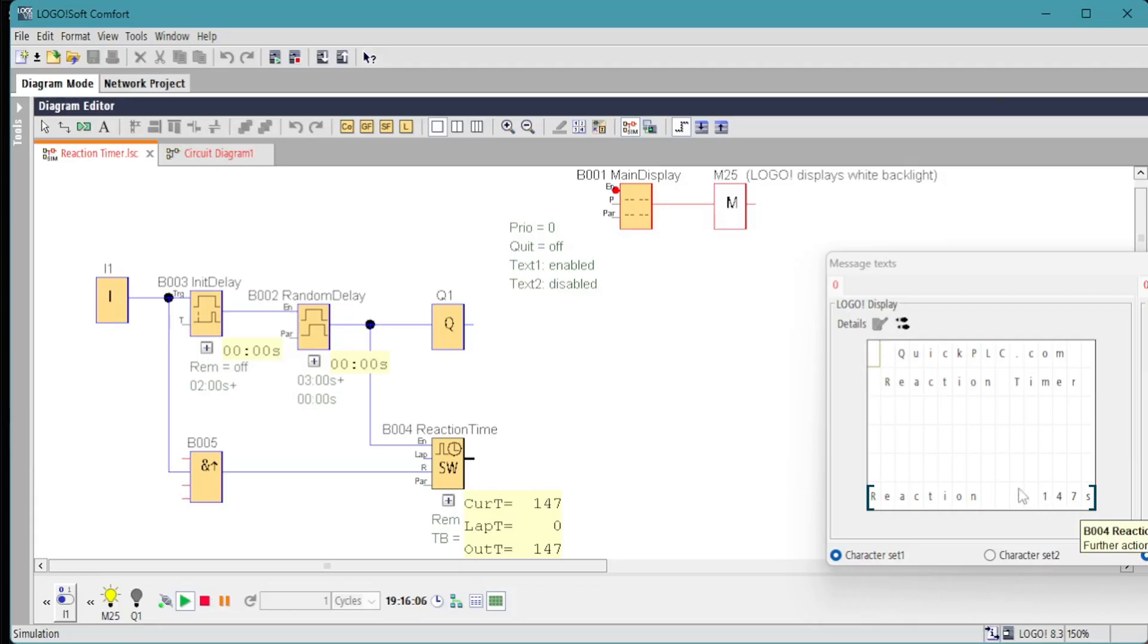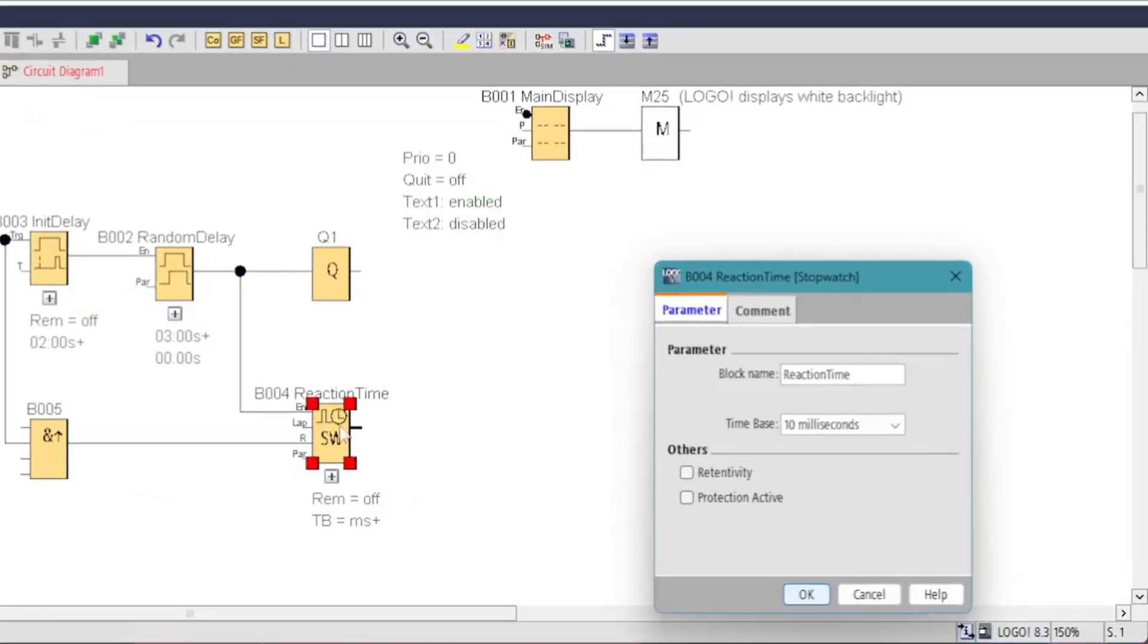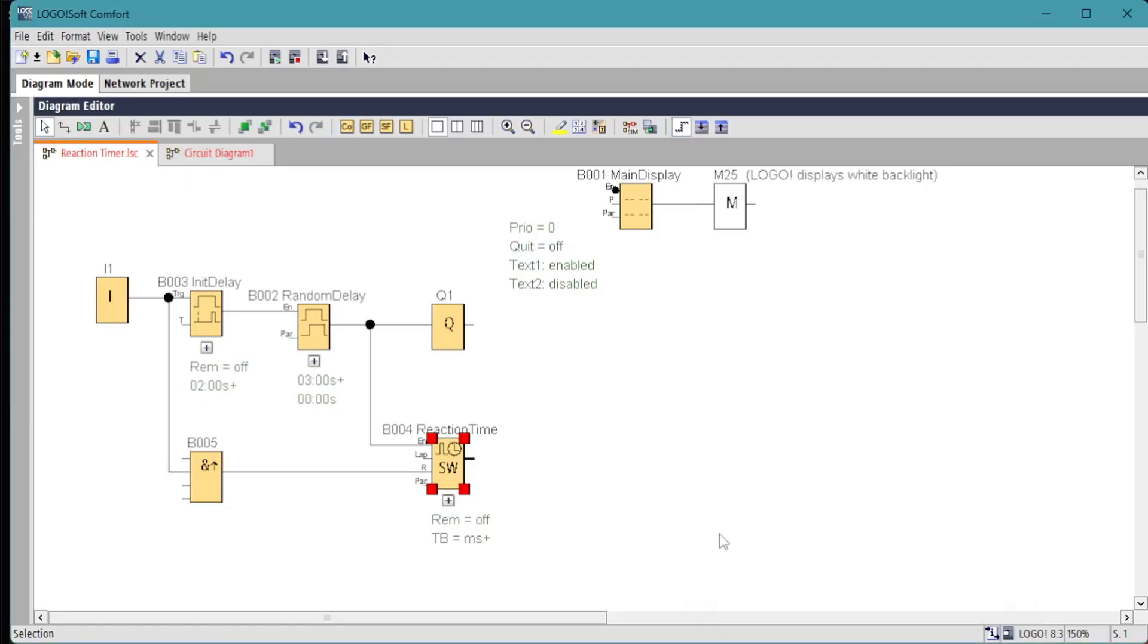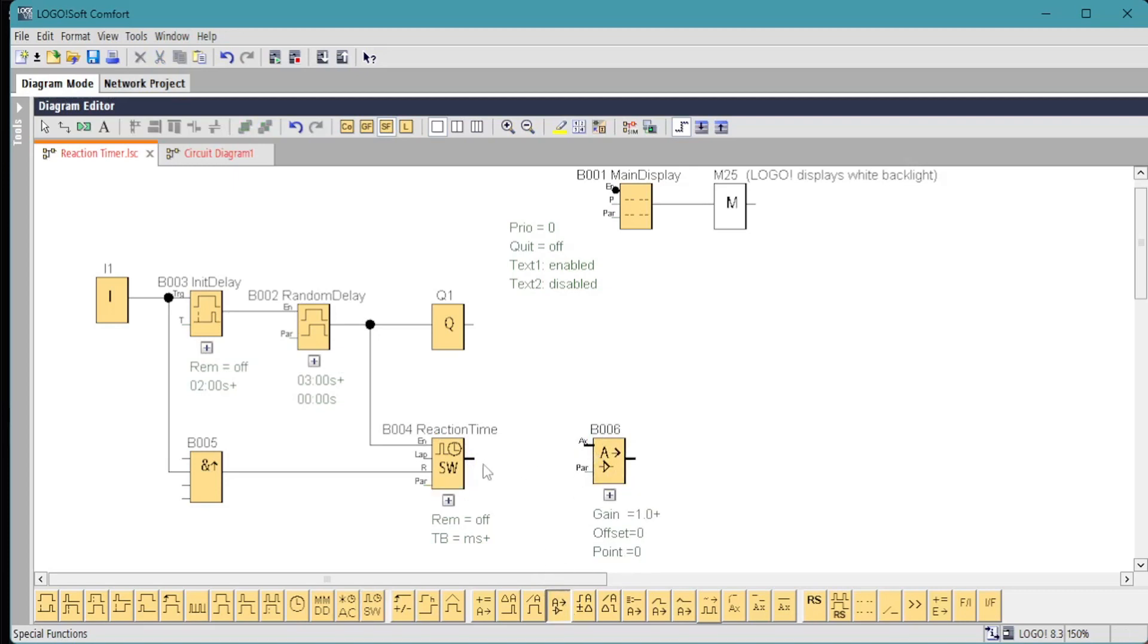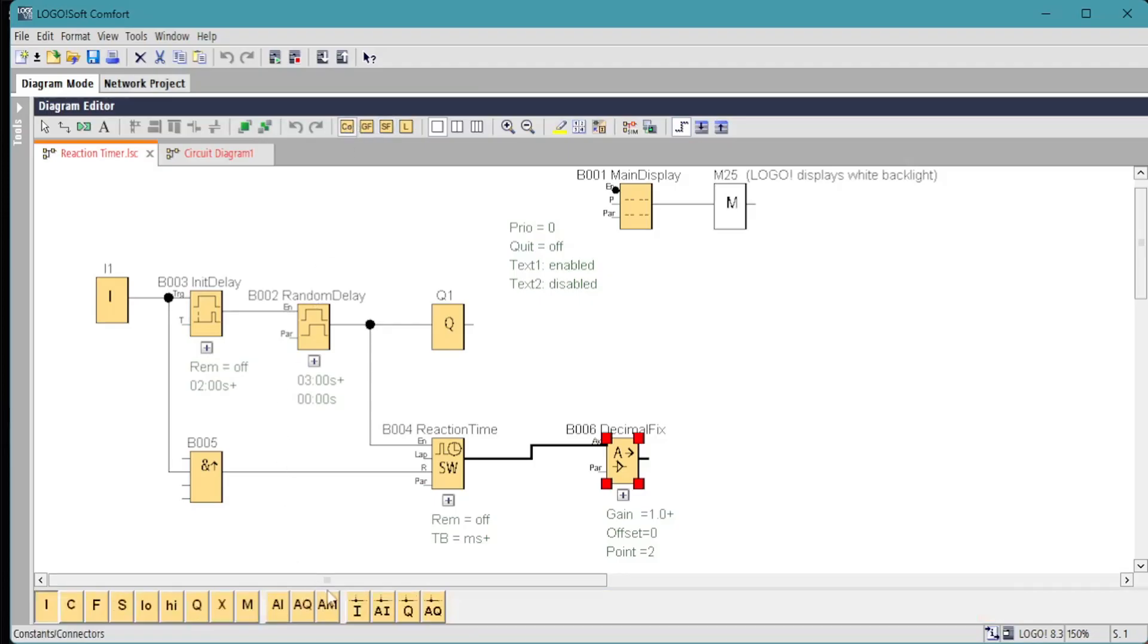Now we would like to display that as decimal seconds, but when we go into the stopwatch we find that there is no feature to change the number of decimal places on the message display as there would be with most of the other timer functions. So we're going to have to resort to a little trick here. There are a couple of ways we could do this. We could use a maths instruction, but this time we're just going to use an analog amplifier. We'll leave its gain and offset at the default settings, so its gain is one, offset is zero. But we'll just use it to change the number of decimal places in the message text.